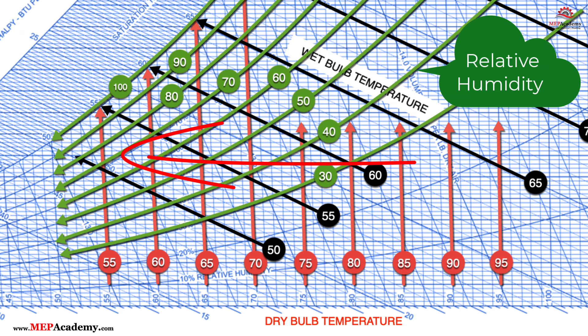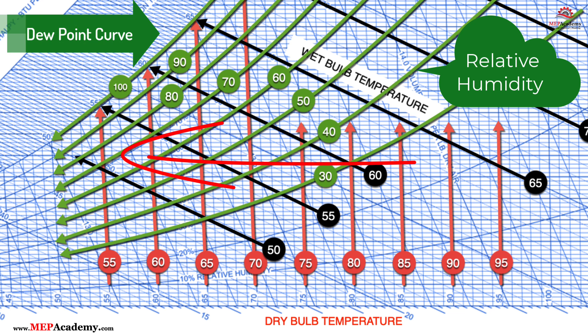This is also the 100% relative humidity line. When the air's dry bulb temperature decreases, the relative humidity increases. If the dry bulb keeps dropping lower and lower, eventually it will hit the dew point temperature. When the air reaches the dew point temperature, the relative humidity is 100%. At this point, the air is fully saturated with moisture and can no longer hold any more water vapor, which is why condensation occurs. Keep in mind, the closer the air temperature is to the dew point temperature, the higher the relative humidity will be.